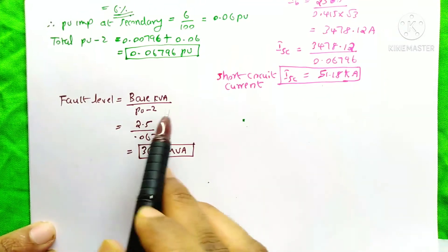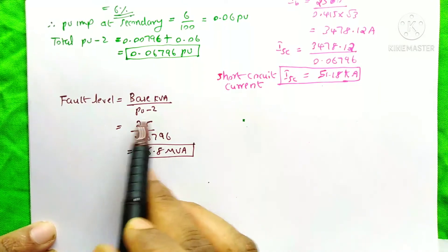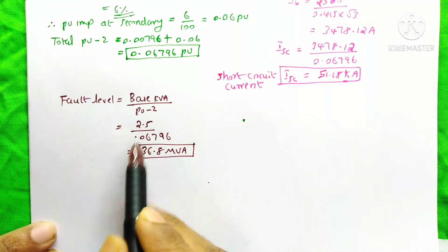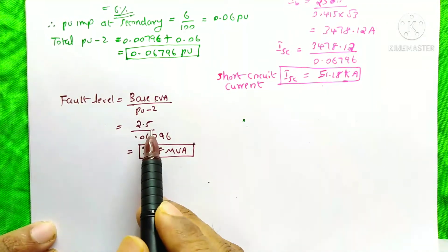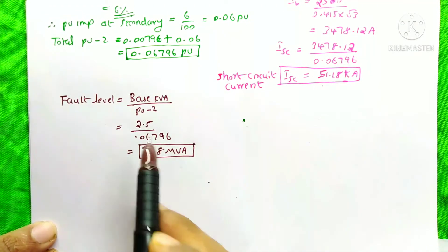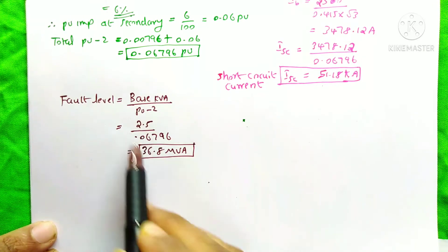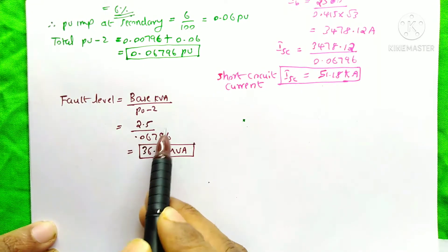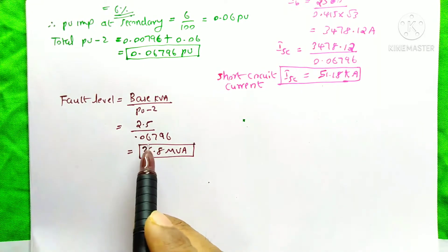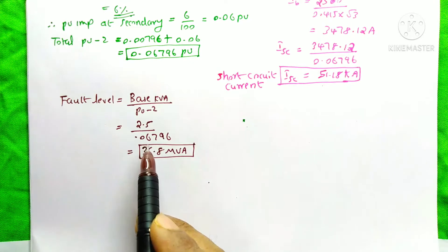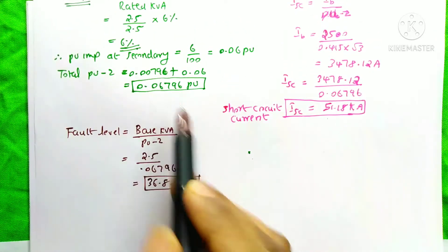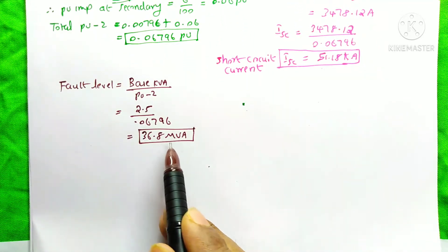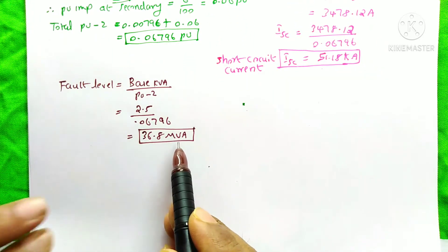The fault level equals base kVA divided by per unit impedance. Base kVA is 2.5 MVA, divided by the total per unit impedance of 0.06796. The answer is 36.8 MVA. This is the fault level at the secondary side of this transformer.